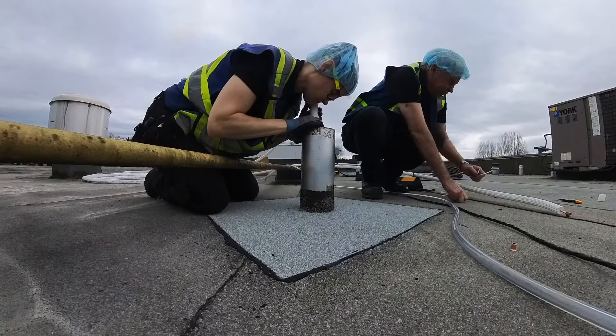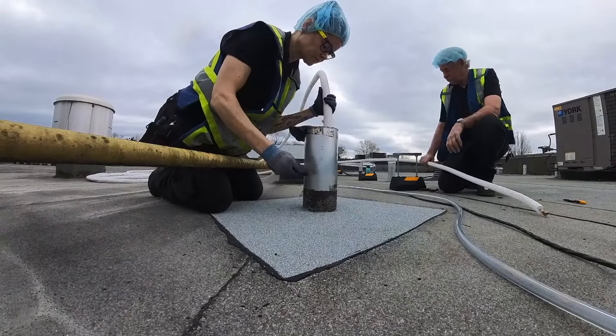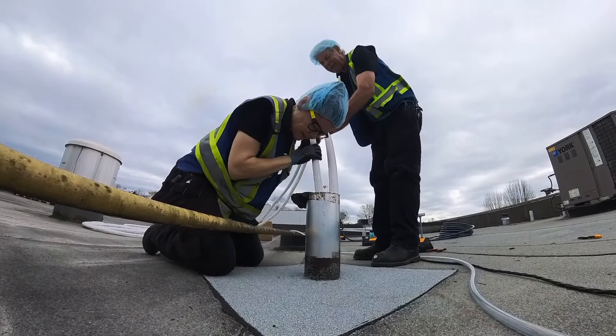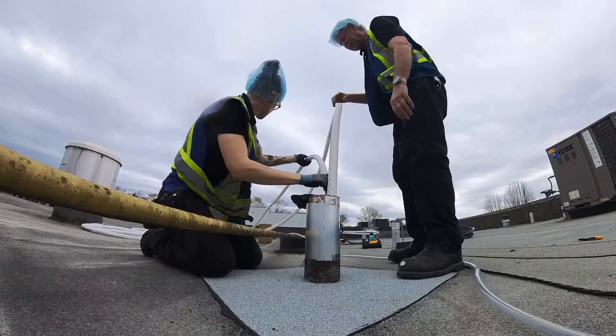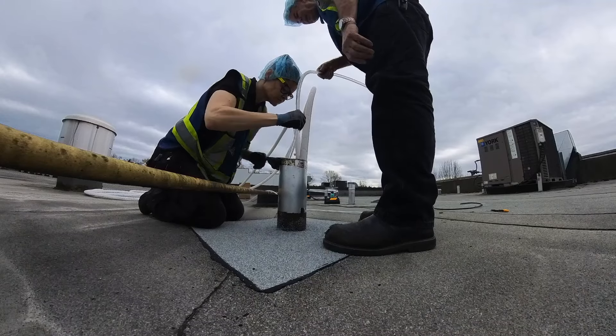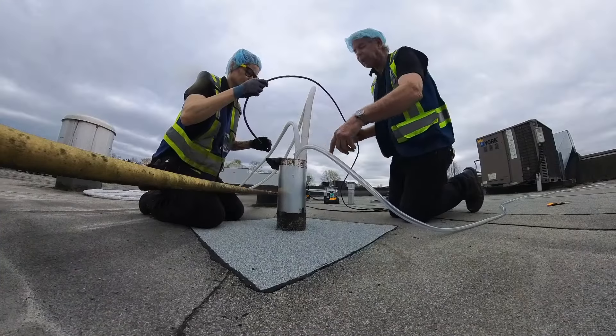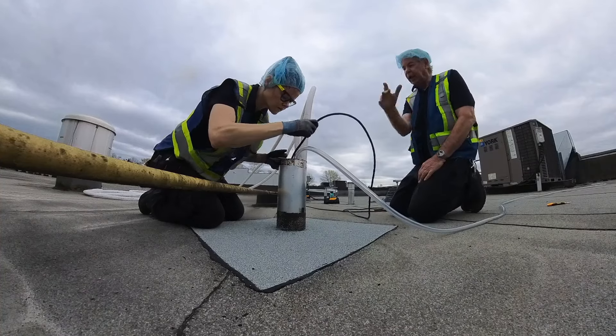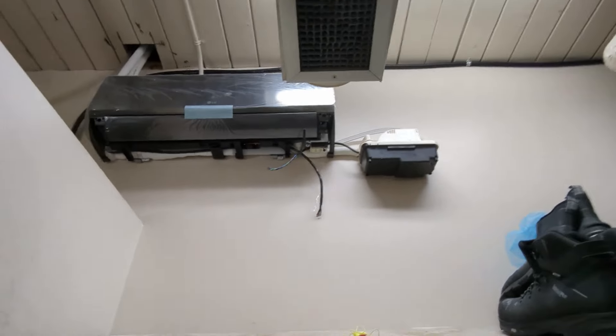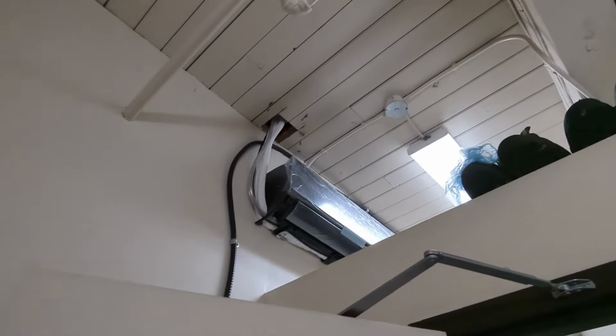I've stayed in the change room to keep working on the things down there, and we're communicating through the roof jack — I can hear him if I put my ear to the hole. Just because this run is so short and we're going through this hole with some other stuff in there, we decided to actually break off the bundle of line set to put them down individually — it just worked out easier that way. So we've got both line sets down. Now we're going to throw the drain line down for the condensate pump, and then finally do the control cable. As I'm setting it down, Trevor's connecting it on the inside. And once he's done his part, we can connect it to the outdoor unit. Look at that beautiful job he's done — everything is tucked away so nicely, the condensate pump is mounted and connected. The only thing he's left for me is the control cable, which I'll come back and do tomorrow.